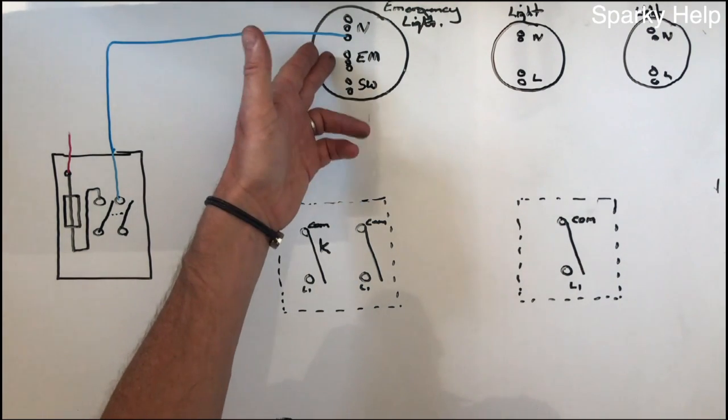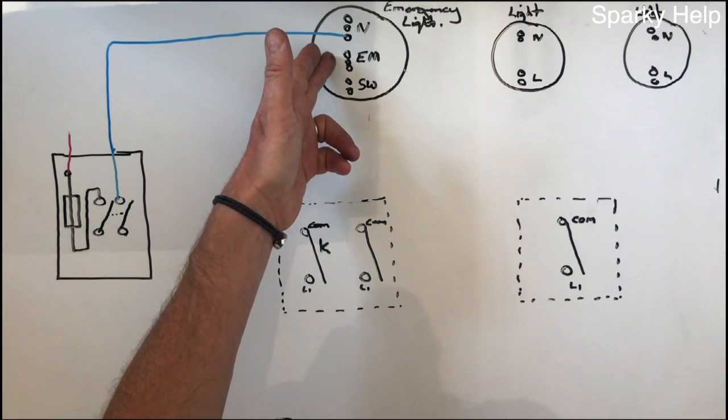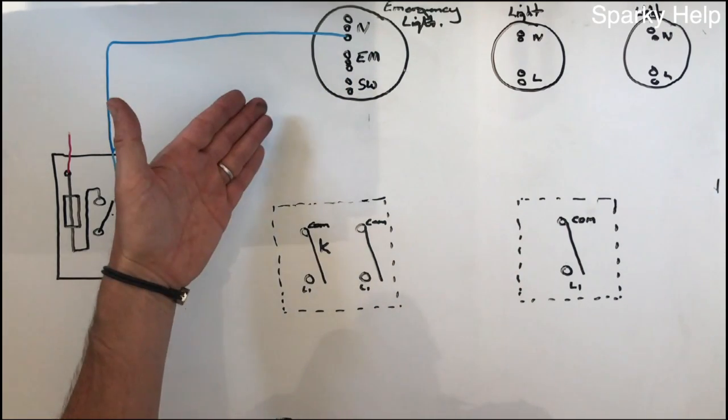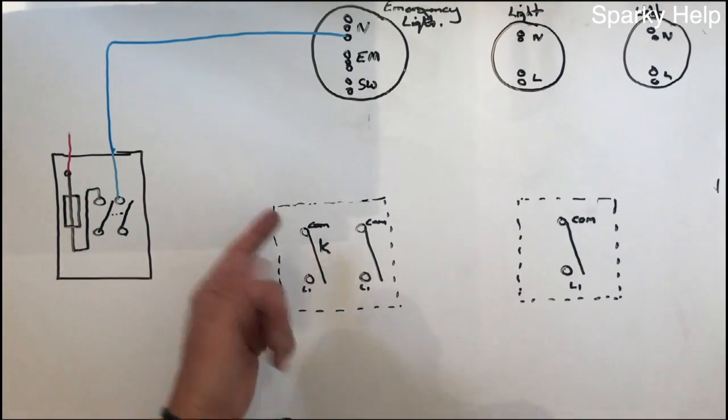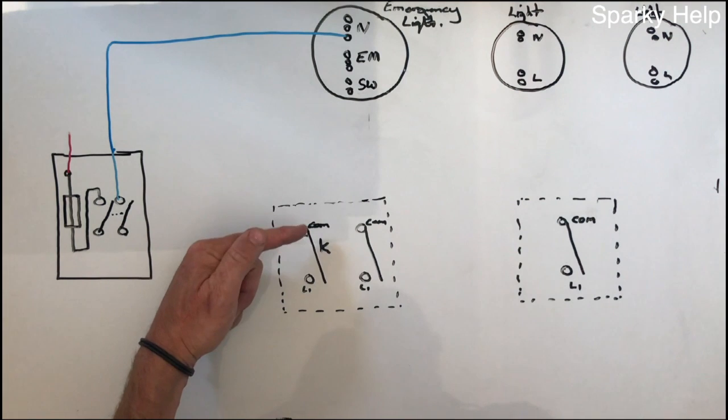But what we need is we need a point to test the emergency, and that needs to be local to it. So typically you'd place that in a switch in the same room, and it would be a key switch, so it would be a key operated switch, but it's still a one-way switch, or a two-way switch, whatever it wishes to be.